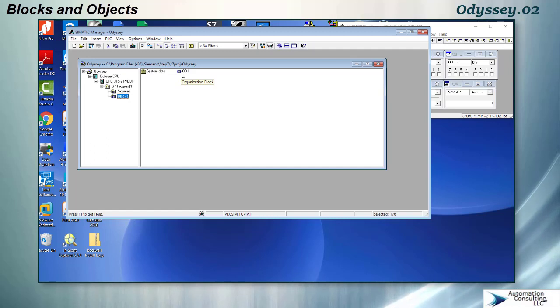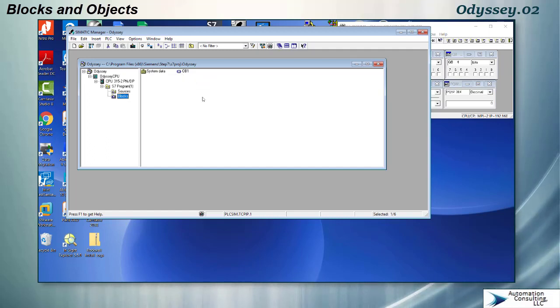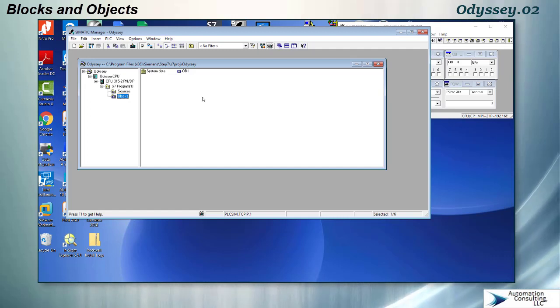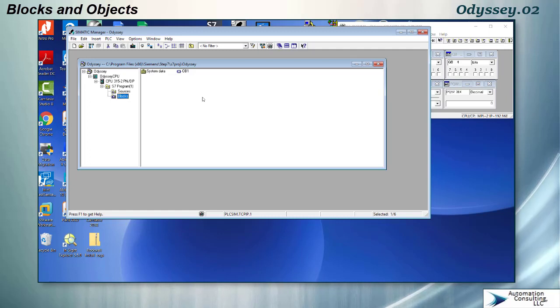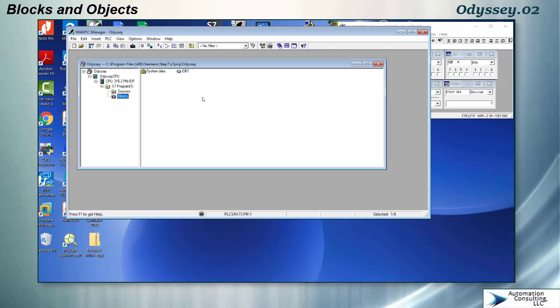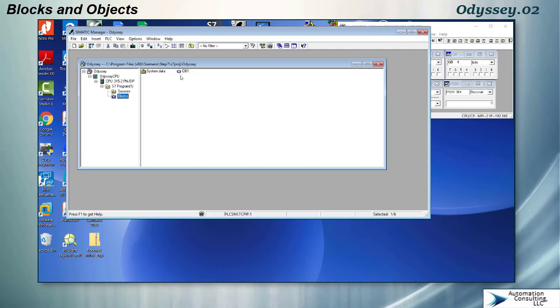OB1 is the main routine in the program. It is a special block, all OBs are special blocks. OB1 has a special purpose, its special purpose is the same as all main routines, it runs all the time continuously. So that's what we're going to do with OB1, we're going to treat it as a main routine and call all other routines from OB1.